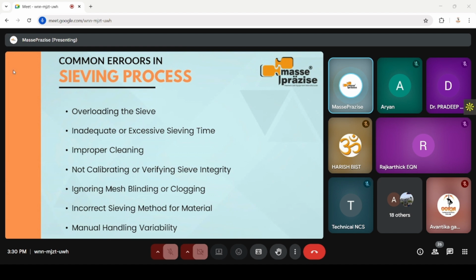Inadequate or excessive sieving time may lead to incomplete separation, that may cause particles to break down further, mesh wear, or unnecessary energy use. Improper cleaning. Cleaning is a very important part of the sieving process, and for the better life of the sieves, we will also discuss the cleaning process separately after this slide. Sieves should be cleaned after every use. Not cleaning a sieve after use or using abrasive tools may cause cross contamination or damage to the mesh that can permanently damage the test sieve.